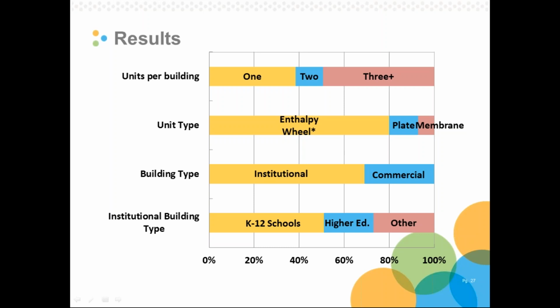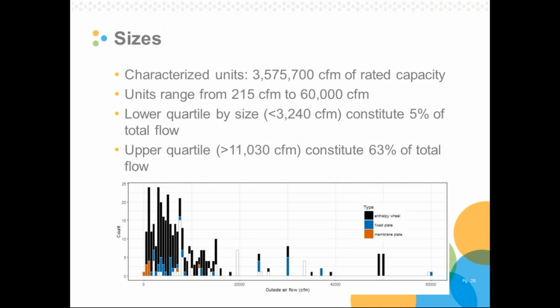It's a slide that I didn't have time to share here, but basically just assuming not the design flow rate, but the smaller of the 2 flow rates in your system will give you a much better understanding of energy savings. So that's one thing we could do when we know we're passing back 10 to 20% less exhaust air. If we just use that flow rate number for estimating savings, we're going to get much closer to the mark than using our design flows.